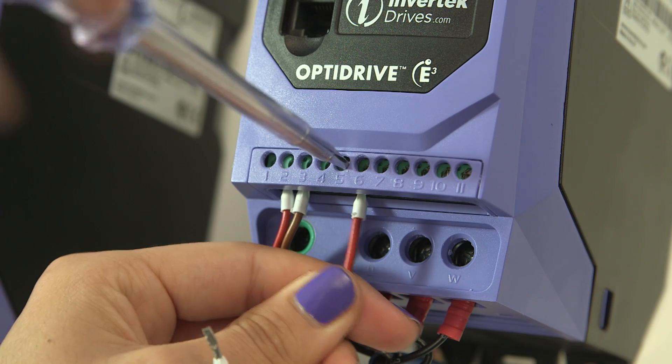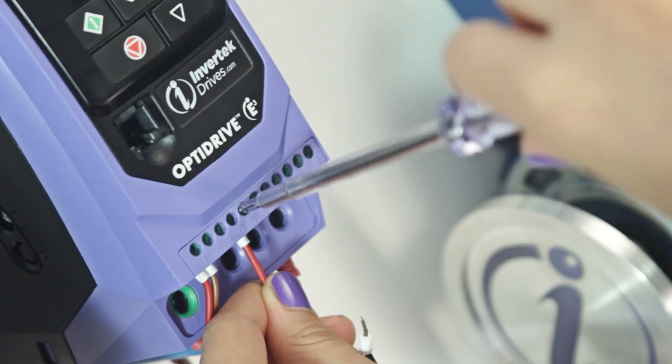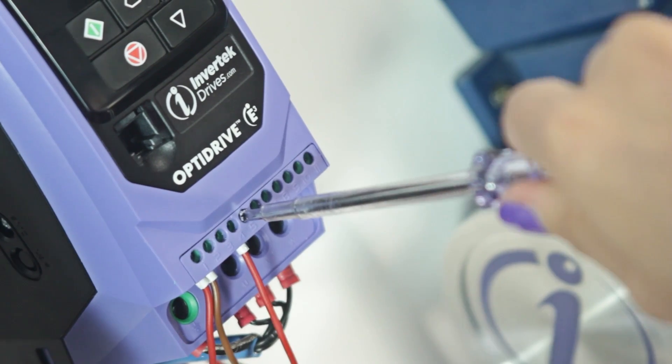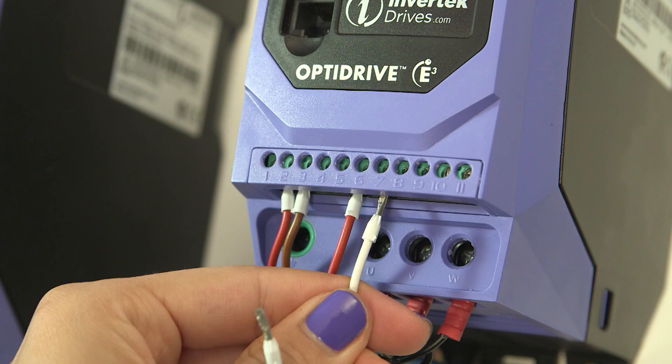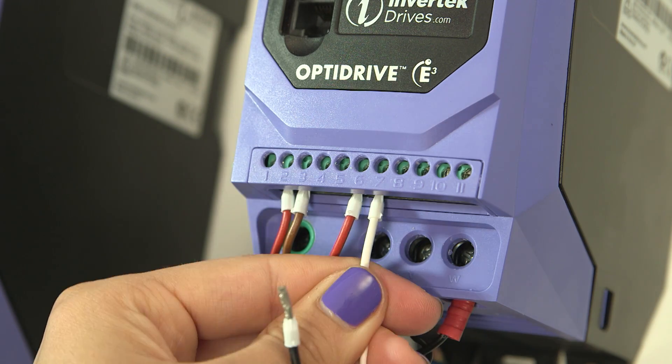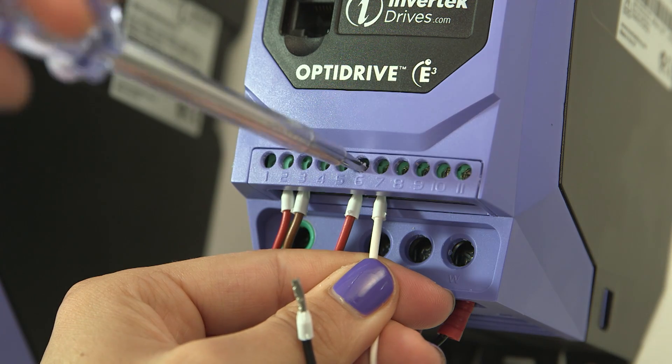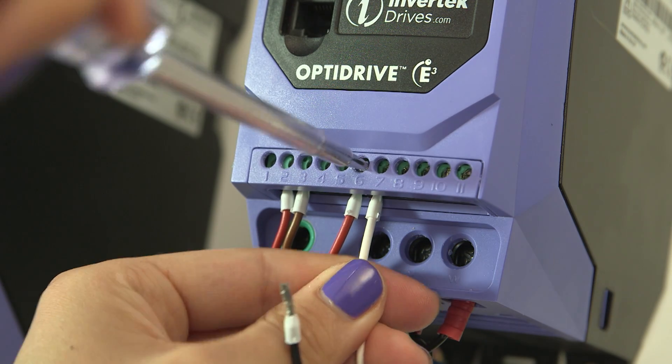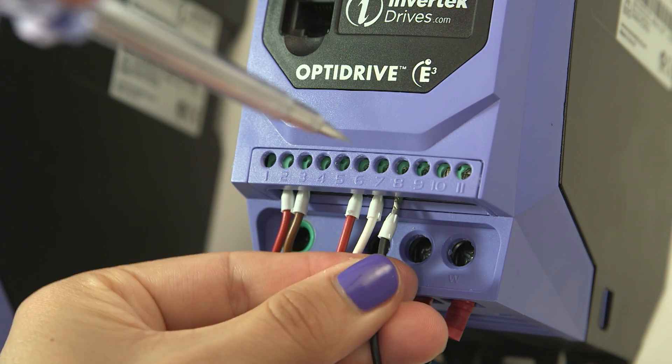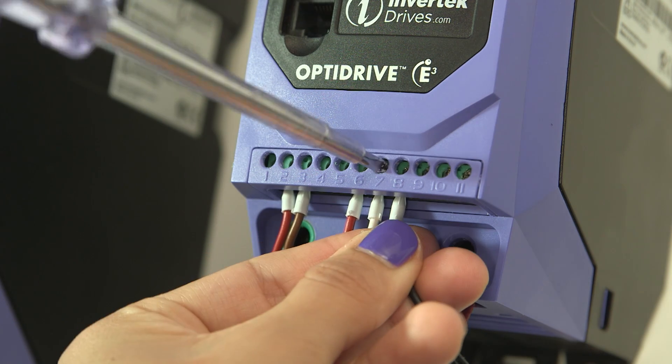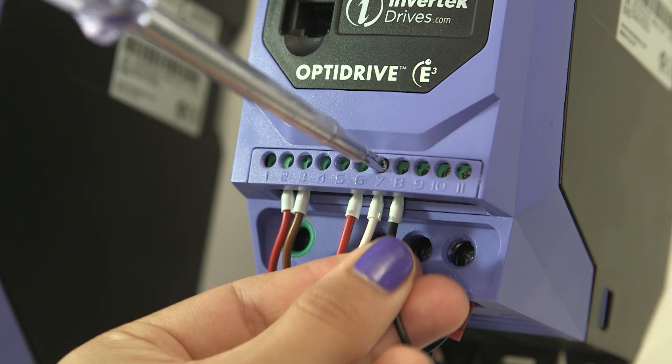Now connect a pot to 5 which is 10V, 6 analog input, and 7 zero volts. The default setting on the analog input is 0-10V, but you can choose many other settings such as 0-20mA or 4-20mA.